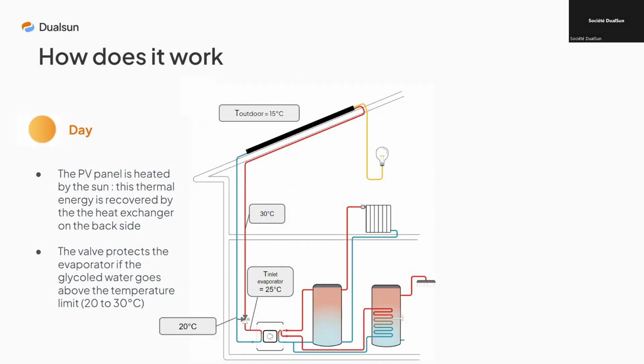For example, here, I start at 20 degrees and recover heat from inside the panels. It's 15 degrees outside, and I leave at 30 degrees, except that, as I was saying, we have a mixing valve to protect the heat pump evaporator, which I've set manually at 25 degrees so that I can mix it efficiently to leave at a maximum of 25 degrees, which is here the maximum evaporator inlet temperature.